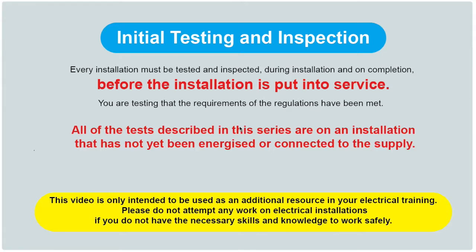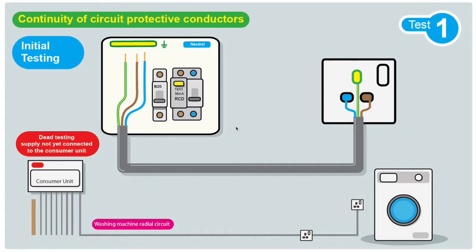This is the first test when you're doing initial testing and inspection of a new installation, and it's the continuity of circuit protective conductors. This is a dead test. The supply is not actually connected to the board yet because you haven't tested the installation.